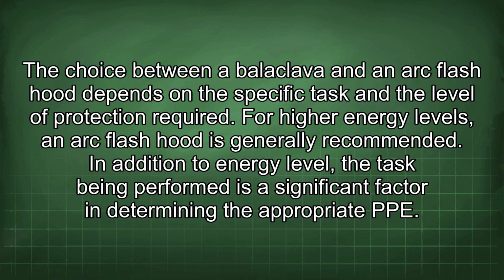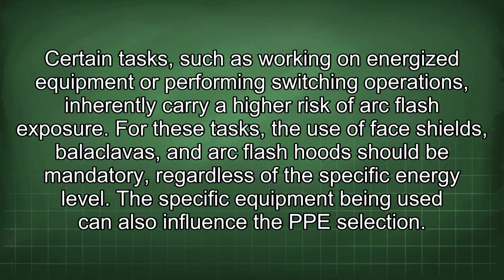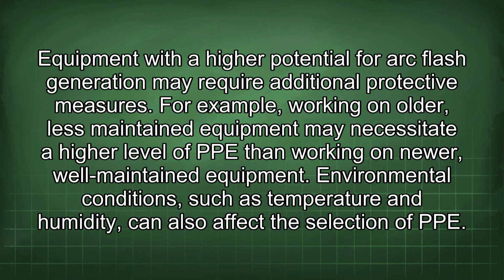In addition to energy level, the task being performed is a significant factor in determining the appropriate PPE. Certain tasks, such as working on energized equipment or performing switching operations, inherently carry a higher risk of arc flash exposure. For these tasks, the use of face shields, balaclavas, and arc flash hoods should be mandatory, regardless of the specific energy level. The specific equipment being used can also influence the PPE selection. Equipment with a higher potential for arc flash generation may require additional protective measures. For example, working on older, less maintained equipment may necessitate a higher level of PPE than working on newer, well-maintained equipment. Environmental conditions, such as temperature and humidity, can also affect the selection of PPE.